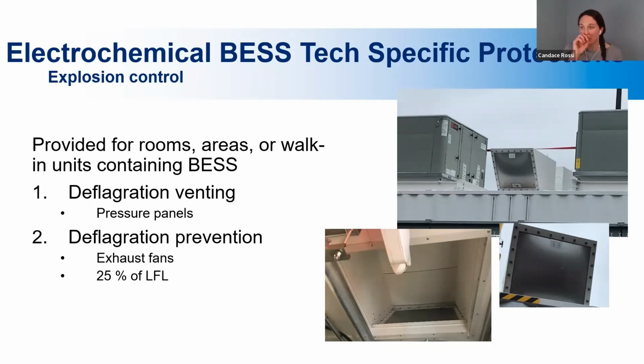Next is the requirement for explosion control, which can be handled in two ways: deflagration venting or prevention. Most lithium ion systems will have deflagration venting panels that manage the pressure blast wave produced in an explosion. The blast wave is sent through the venting panels while maintaining the integrity of the container. These panels' venting directions should be directed to areas that won't interfere with fire department operations. As discussed earlier, while not required for normal operations, exhaust ventilation can be used for lithium ion systems as part of their explosion prevention.